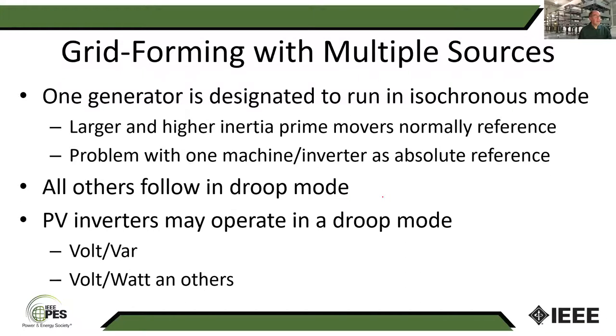And so if you have multiple sources, you may have one generator or one inverter that's designated to run in isochronous mode. If it's a rotating machine, you would want one that's larger and has higher inertia in its prime mover. If you have that one machine acting as the absolute reference, that has some advantages, but it also has disadvantages, right? Then it becomes sort of like the equivalent of your mathematical slack bus in your power flow solution. How are you going to keep that from being overloaded? How do you handle power limits on it?